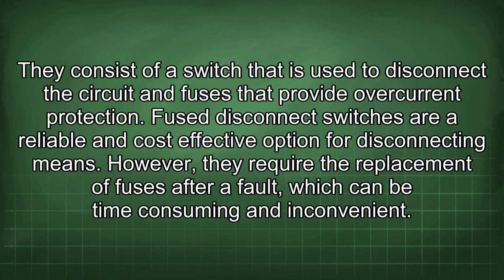Fuse disconnect switches provide overcurrent protection and disconnecting means in separate devices. They consist of a switch that is used to disconnect the circuit and fuses that provide overcurrent protection. Fuse disconnect switches are a reliable and cost-effective option for disconnecting means. However, they require the replacement of fuses after a fault, which can be time-consuming and inconvenient.